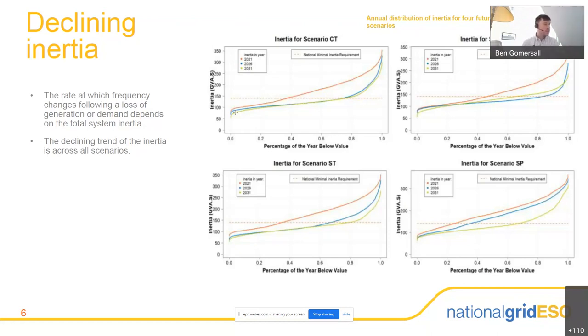So the orange is the current year, the blue is 2026, and the green is 2031. So you can see across them, the data is moving down, which is showing the decrease in inertia. And it's also staying lower for longer, which is the shift to the right in the graphs as well. So that's the real challenge that we're seeing at National Grid, or on the GB system as a whole, that inertia is lower and it's operating lower for longer.